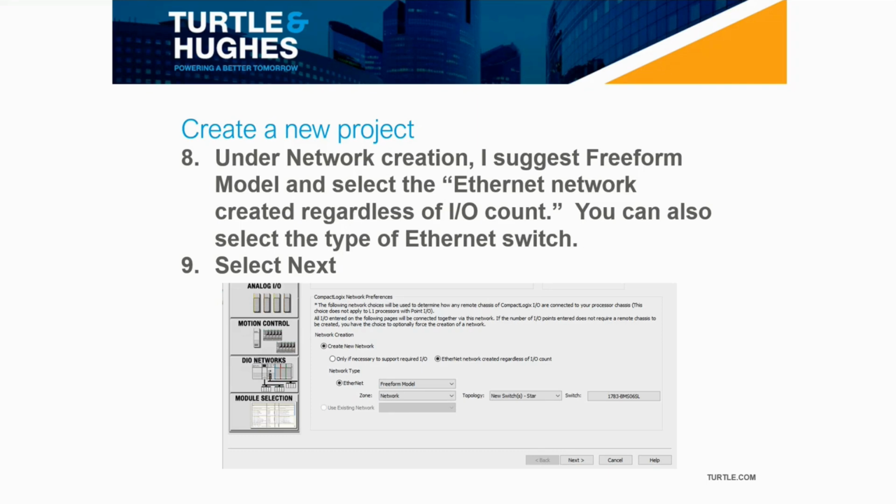And then you have a choice as far as, well, what kind of Ethernet network do I want to create? Now, if you're dealing with a CPWE type of layout where you've got distribution switches, access switches, managed switches, a real hierarchy, you use that choice. But typically, I'm not usually at that level. So I say I want to use a free-form model. What this allows me to do is create that network in a much more relaxed fashion without applying those CPWE rules, which is frequently what I run into in the projects that I'm working on.